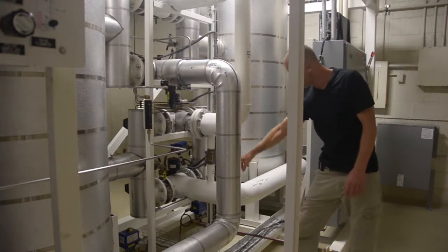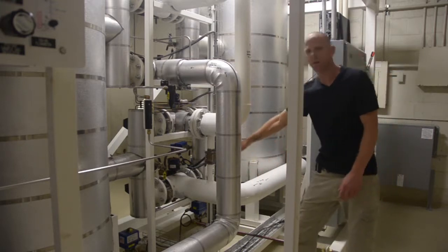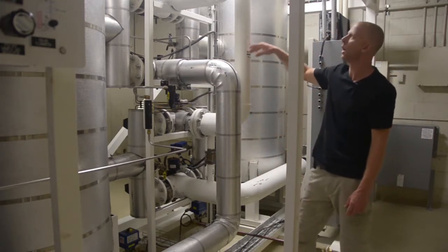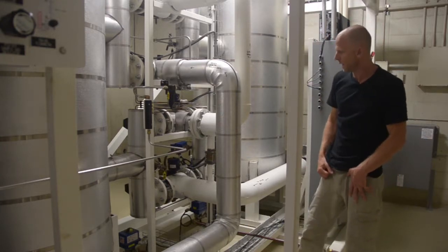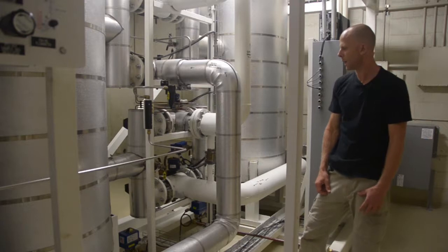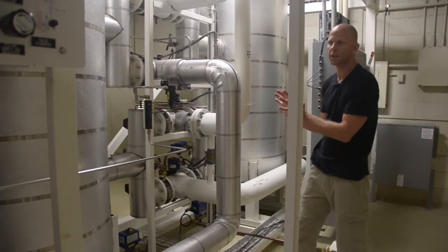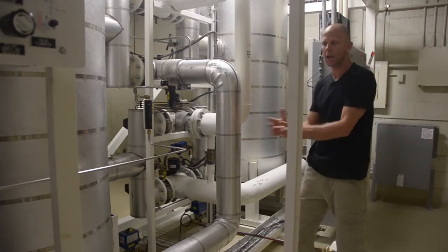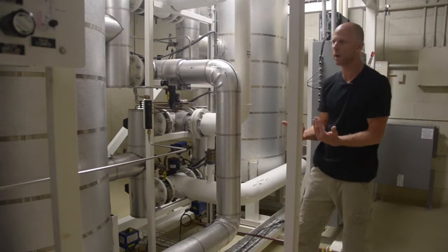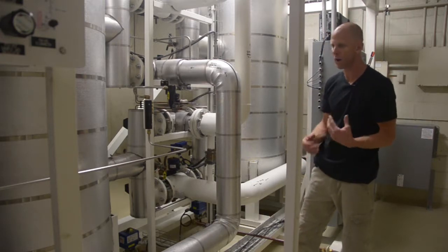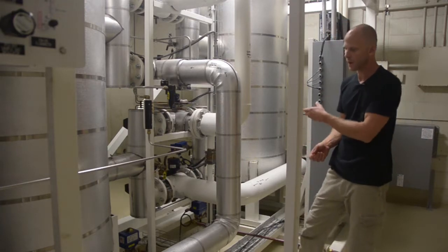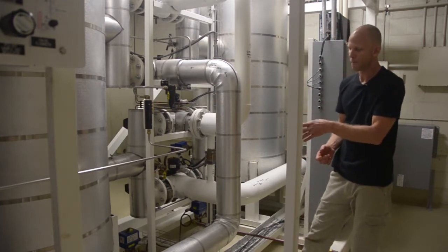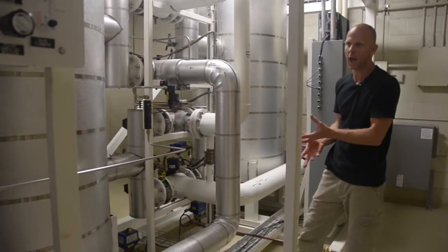So we can bypass process air from our process air line, high pressure air, into atmosphere basically. And we would do that under certain circumstances where the plant itself was not taking much air, there was not much airflow through the plant, maybe the cold box is closed, maybe we're doing an initial bed regeneration process, maybe we're pressurizing a bed, so there's only a very small process flow being allowed into the plant.